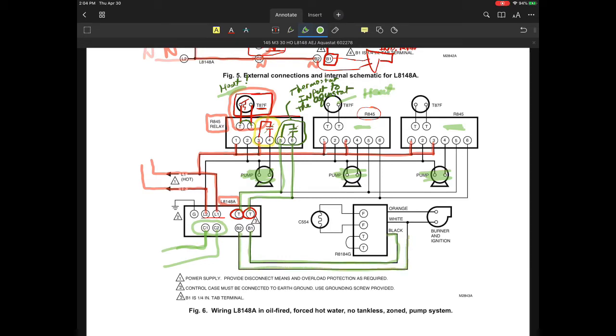Now the burner circuit, B1 and B2, B1 is going to provide, as we saw earlier, my line voltage into an oil burner, and B2 is nothing more than your neutral. And you'll notice that they tied that into the white wire, which was also going to a burner or ignition control or something like that. This is what they call in oil systems, this one's your primary control. That's what that is. So that's actually going to be what I'm going to call my primary control.